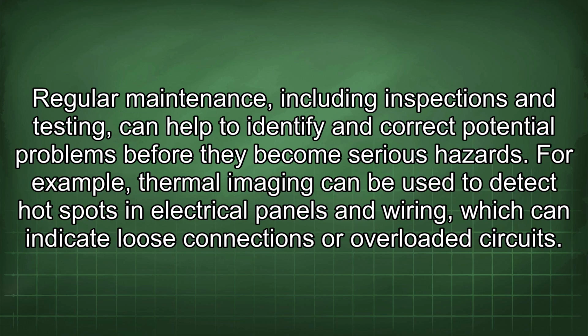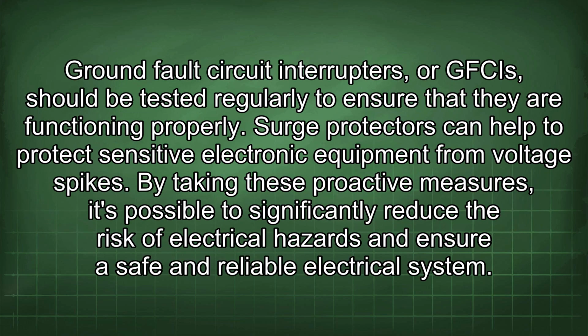For example, thermal imaging can be used to detect hot spots in electrical panels and wiring, which can indicate loose connections or overloaded circuits. Ground fault circuit interrupters, or GFCIs, should be tested regularly to ensure that they are functioning properly. Surge protectors can help to protect sensitive electronic equipment from voltage spikes. By taking these proactive measures, it's possible to significantly reduce the risk of electrical hazards and ensure a safe and reliable electrical system.